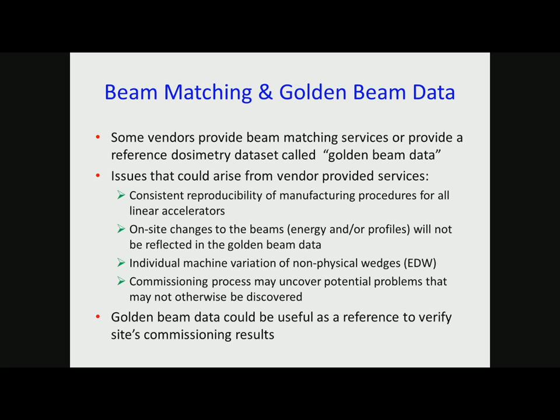The wedges may work differently. The commissioning process may uncover potential problems that may not otherwise be discovered. And so it's very important that you thoroughly commission your Linac, and then you can use the golden beam data to compare against the data you got.